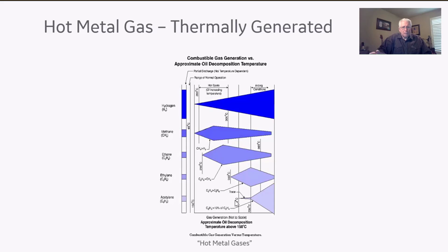And without arcing, you can thermally generate acetylene if you start hitting temperatures greater than 500 degrees C. Once you get to about 700 degrees, you're in the process of flashing over. So a lot of times you'll see some of these gases, and you may see one or two parts per million of acetylene. That doesn't necessarily mean you flashed over. It could mean that you've just hit the 500 degrees C temperature. Neither of those conditions is good, but it is something to consider, because a lot of times we think, well, if we see acetylene, we flashed.